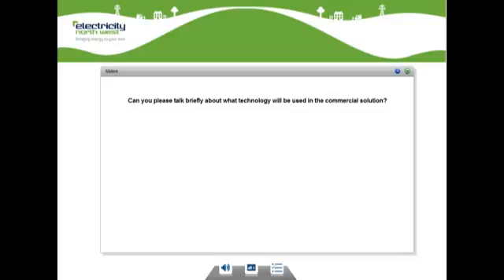As I say, until we identify customers that are willing to join the journey with us and understand what we can do, until we get to site and see what's there, it's very difficult to say what technology we need to install. The ideal easy solution would be where they've got a modern numeric relay and we can apply a second setting group, which we would enable via an input onto the back of that relay, possibly by some sort of 3G system. Probably for safety reasons, we will be looking for adaptive protection to be the fail-safe mode, i.e. if there's no signal from the system, it stays in adaptive protection mode, and it needs the signal from the system to stay off adaptive protection mode to make sure this is a fail-safe solution.